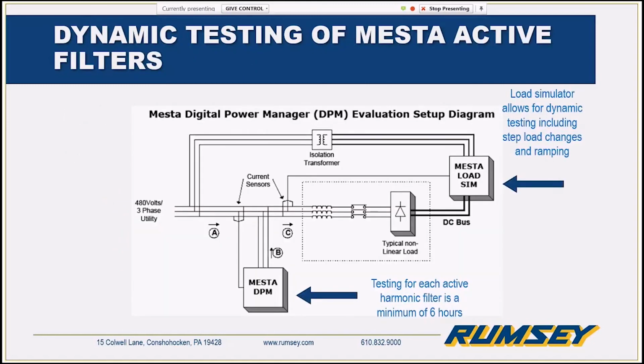We always like to spend some time talking about the testing of our units and also how we're different from older active filters or other brands you might be familiar with. So just to look at this little drawing, we have our active filter with our CTs. We have a load simulator we use, and with that load simulator, we are ramping up and down like a VFD would. We're initiating step load changes. We're making sure that we're responding within a half a cycle. So right up there, industry leading half a cycle response time.